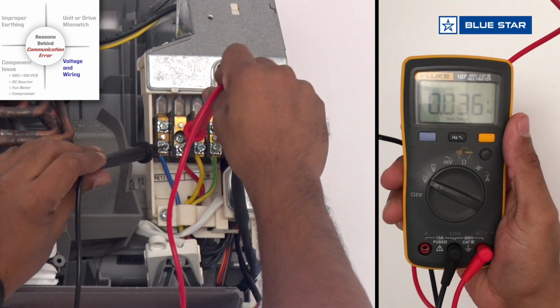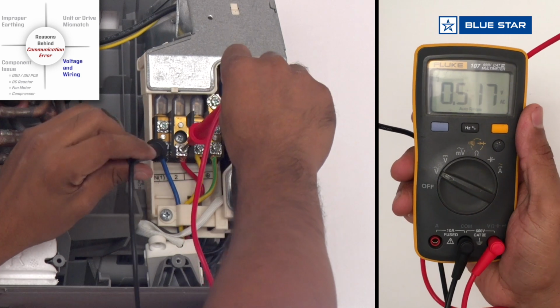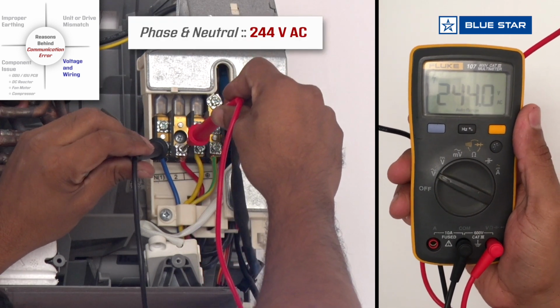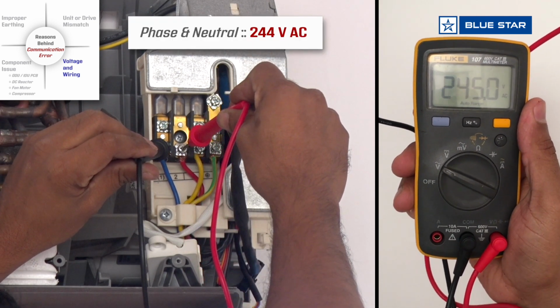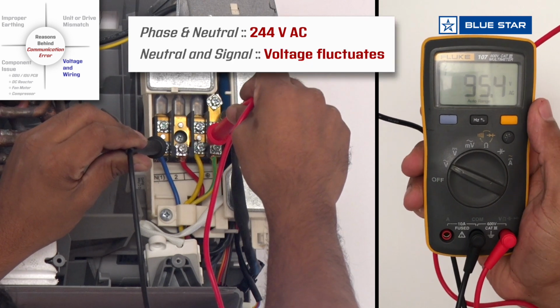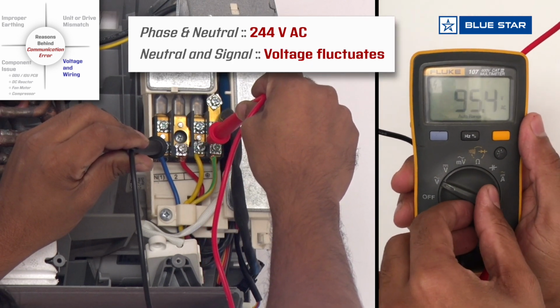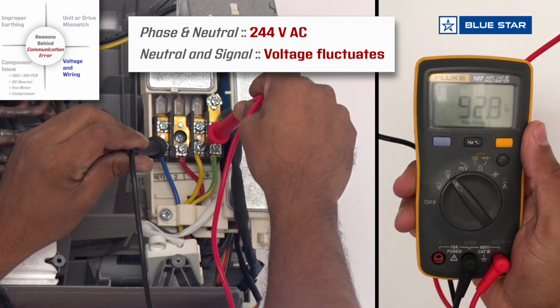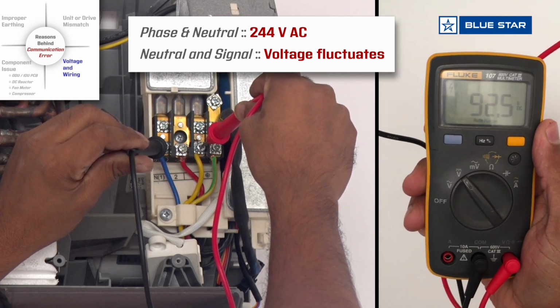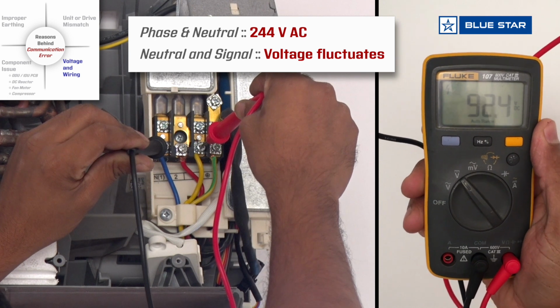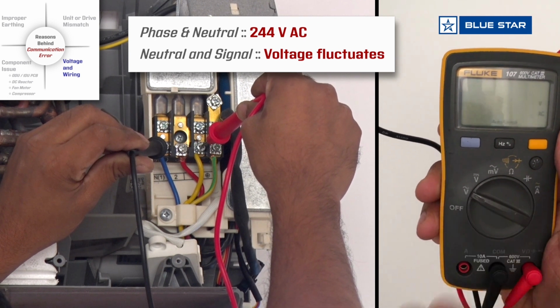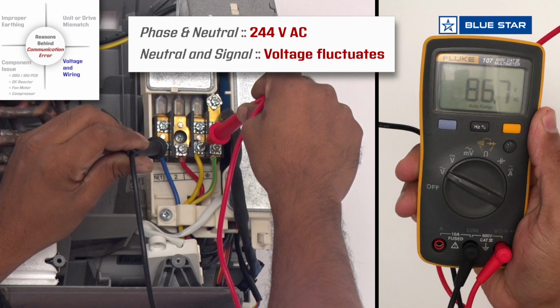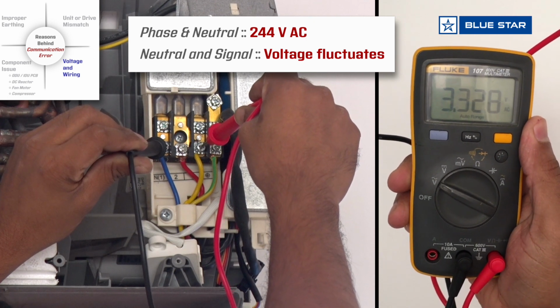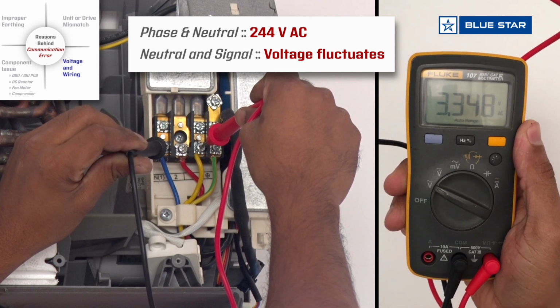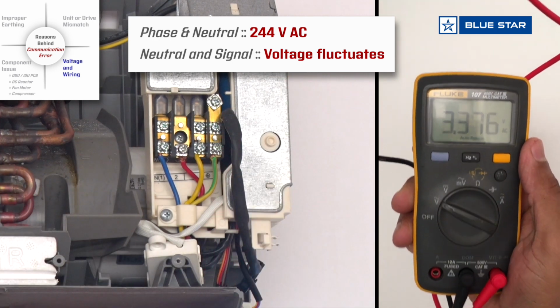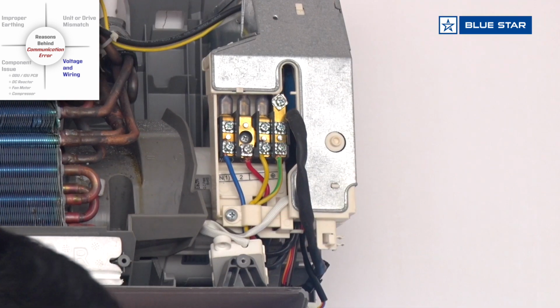If connections are proper, then check AC voltage between phase and neutral. It should be between 220 to 240 volts. Now check the voltage between neutral and signal. In healthy condition, AC and DC voltage fluctuates. In case of any issue, it shows constant voltage. If we get constant voltage, then we need to check the IDU PCB. To do that, remove cables and check voltages between phase and neutral and signal.